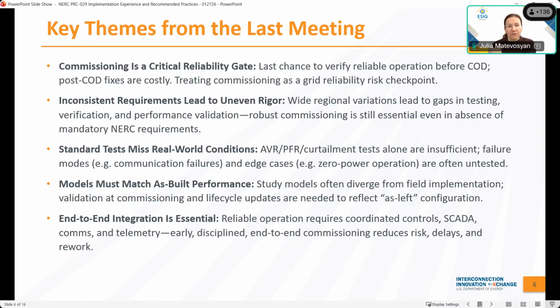Inconsistent requirements lead to uneven rigor. There is a wide variety of what's required during commissioning testing, verification, and performance validation. And so even if NERC standards around commissioning testing do not exist, or if in your area there are no robust commissioning test requirements, it's still essential to do this testing, even for the sake of the plant operating reliably and not having issues after commissioning.